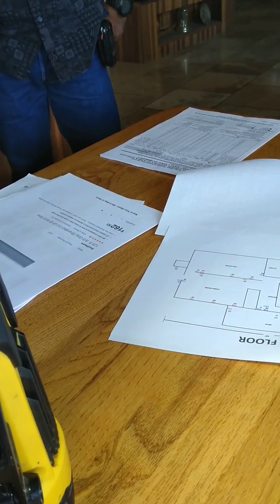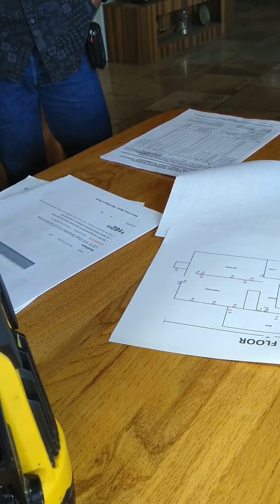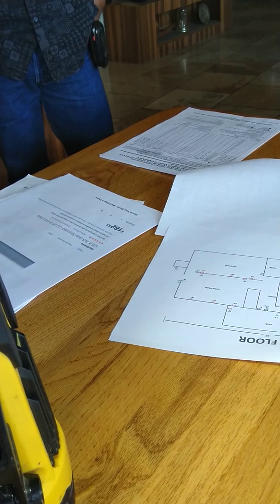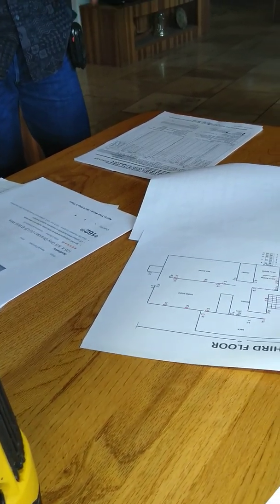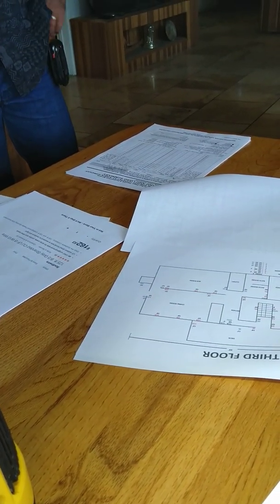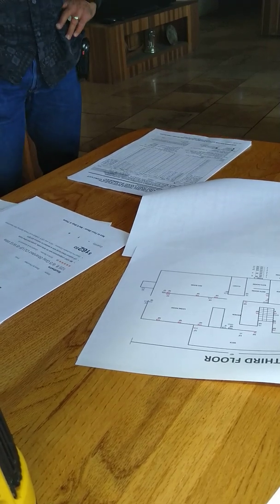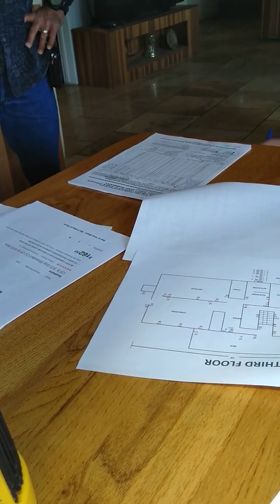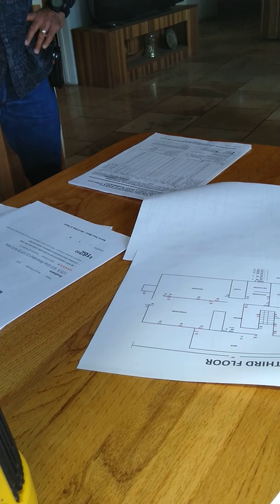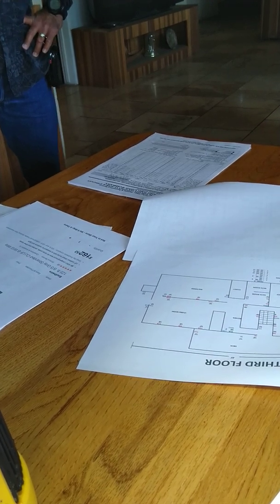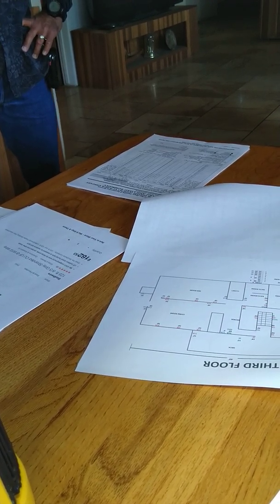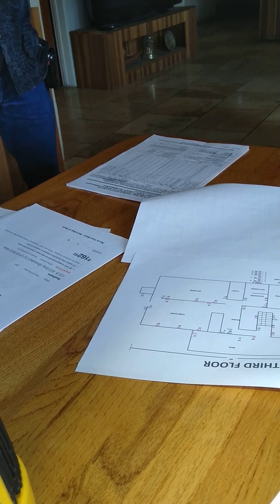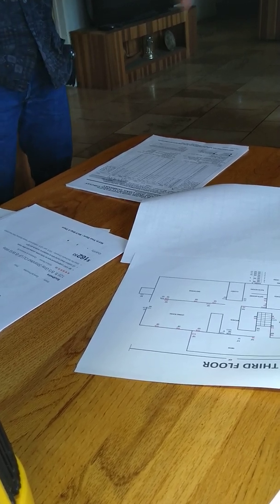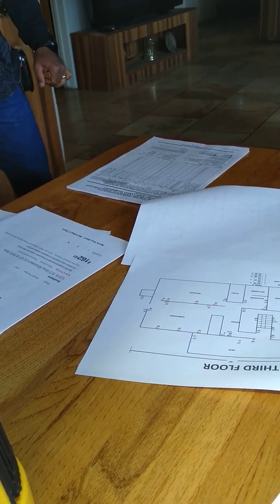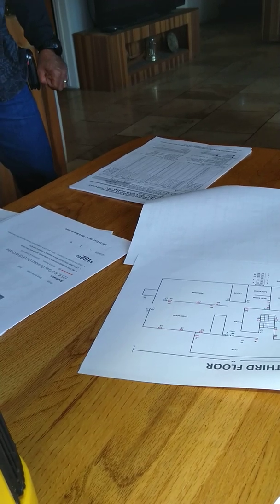So I don't think the number 8 is the proper number. 8 gauge is probably too small on some, not all. The one I was talking about just goes to the swimming pool, where there's a pump and lighting. So anything less than 40, you're probably okay on that. Sometimes, not to muddle this up, if it's a real long distance, you lose some of the amperage, so sometimes you have to upsize it.